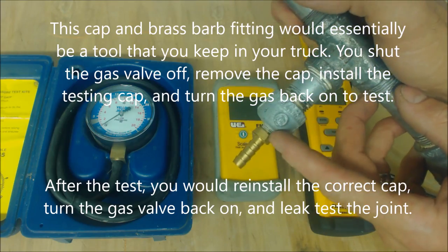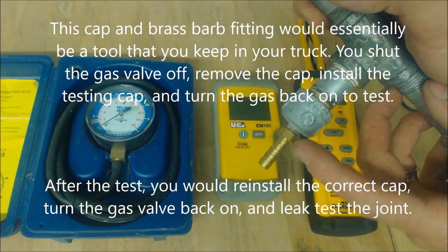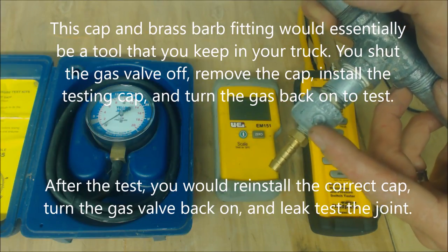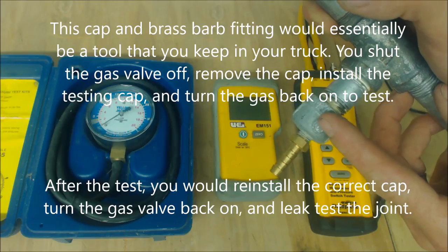We could also check it at the drip tee right here. We could have a cap with a brass barb fitting already tapped into it and check the gas pressure there while the furnace is running.